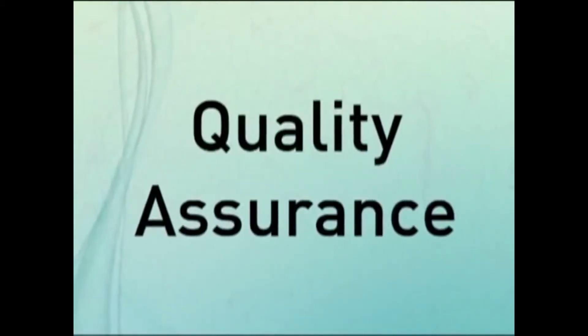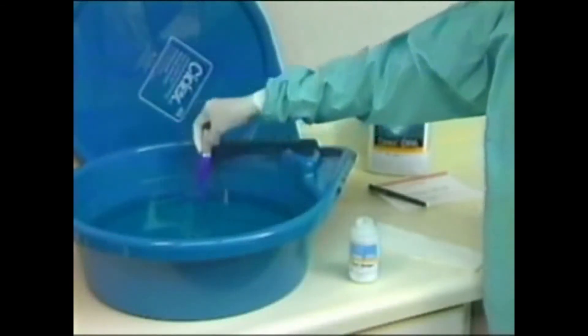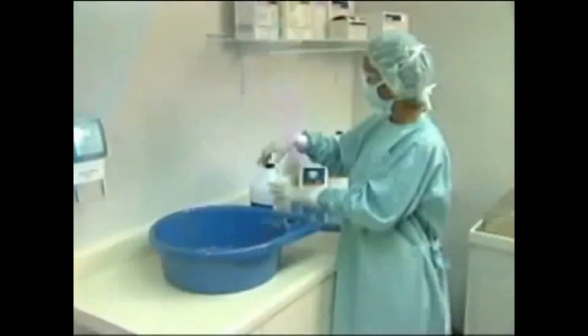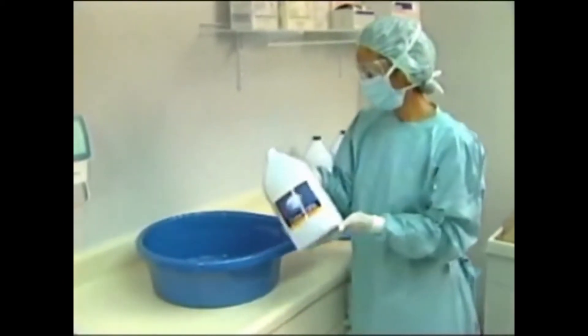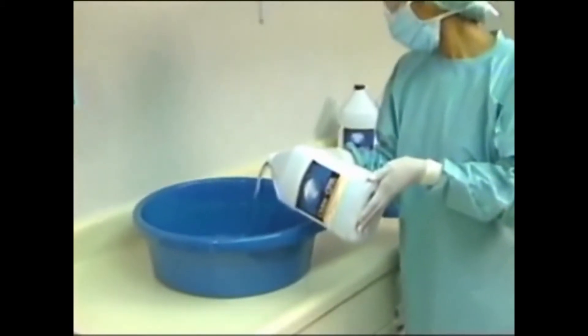Quality can be assured by the proper use of Cidex OPA solution test strips. The solution must be tested using the test strips to verify that the minimum effective concentration is still present. Once Cidex OPA solution has reached either the end of its 14-day reuse life or the minimum effective concentration, or MEC, the solution can be discarded down drains in accordance with local and state regulations.